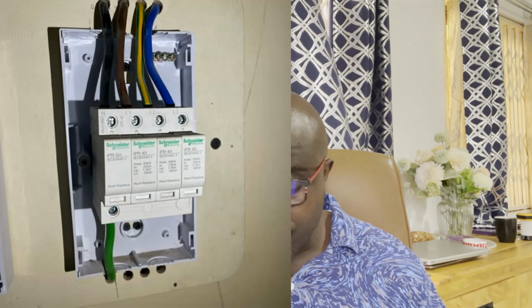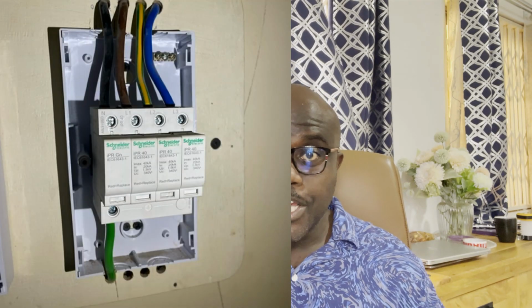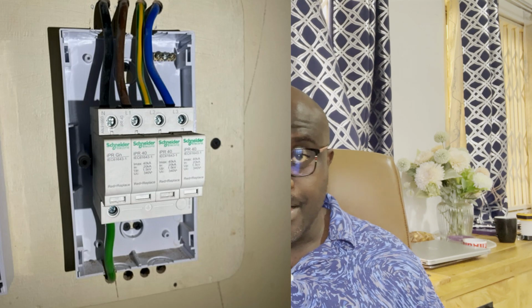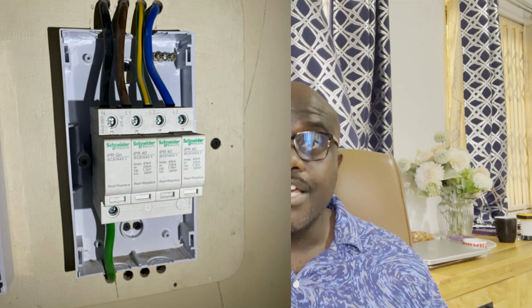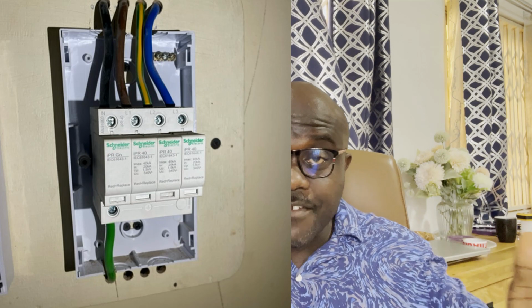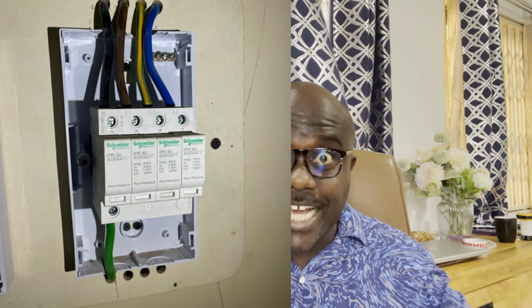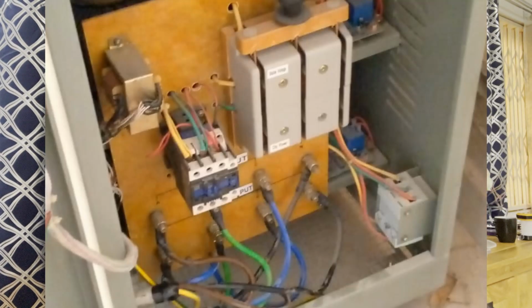The 63 amp changeover was changed to 100 amp. The SPD was wired with all 4 phases. The Havells breaker was changed from 63 to 100. All the small cables were changed to the right size as the other incoming cables, all 16 mil. The AVR was the 3-phase AVR. Guess what, guys? It was wired as 3-phase, as it should be. The metallic chassis of the AVR was connected to earth now, so that was all nice and safe.